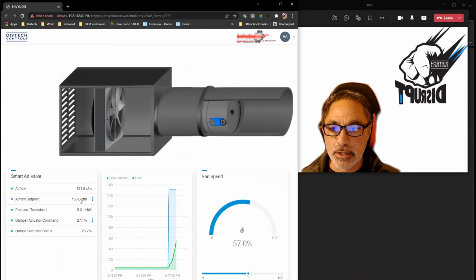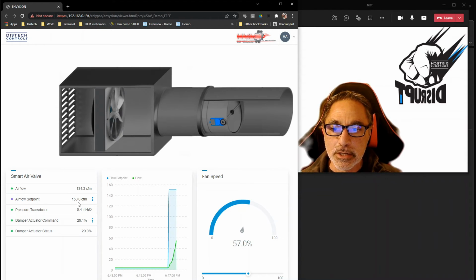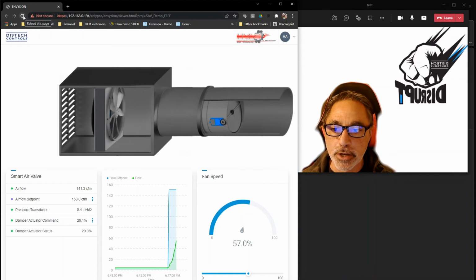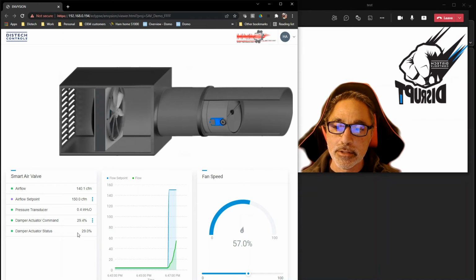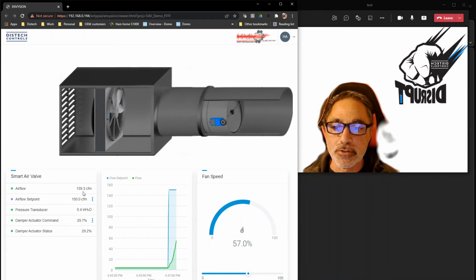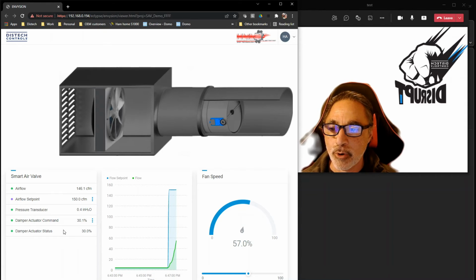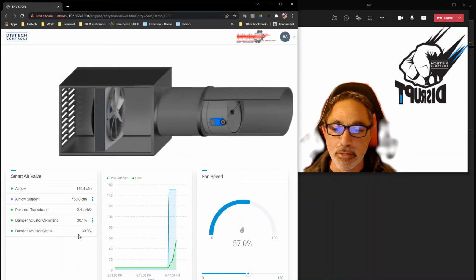So as you can see here, this is climbing and it's trying to get to that 150. One of the things I've noticed about this product, which makes it very impressive to me, is it doesn't do a whole lot of overshoot or undershoot. The algorithm running inside this controller does an excellent job of understanding where it needs to be, and it starts throttling back the actuator to make sure it's very precise to the CFM that you're asking for. As you can see, it's really not opening that fast. It's incrementing in 0.1 to 0.2%. And we have a true feedback coming back right now around 30%.